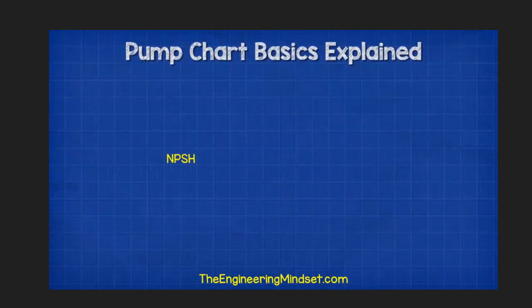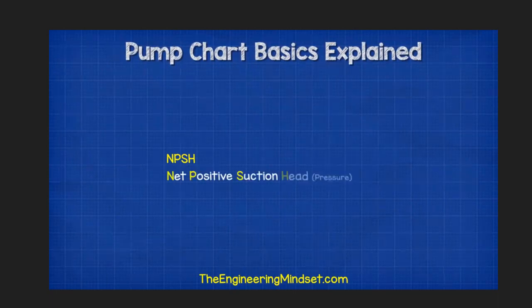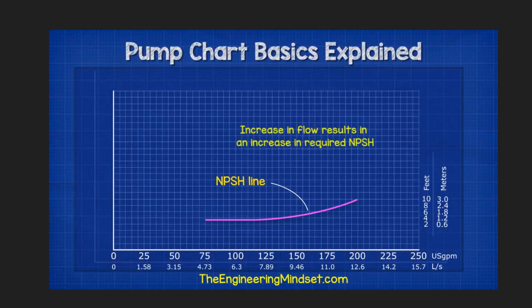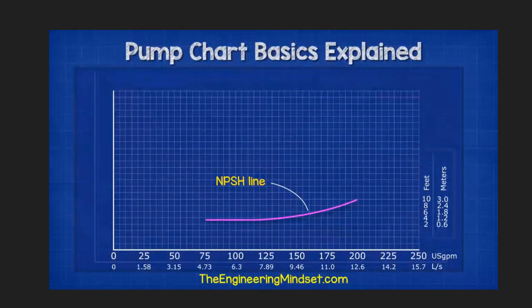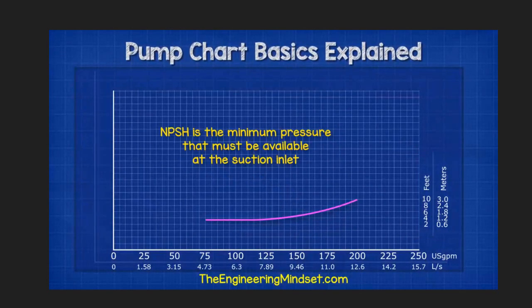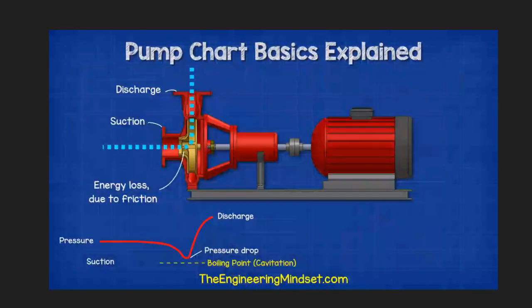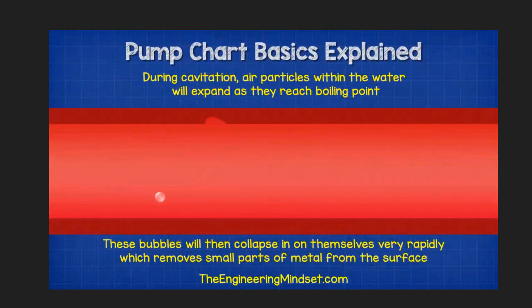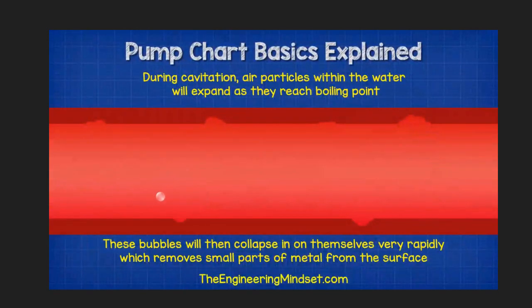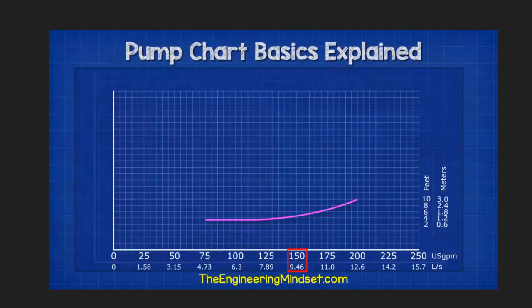NPSH is the required net positive suction head pressure. It usually has an upward curve, meaning as the pump flow rate increases, the NPSH value also increases. We measure this in meters or feet, sometimes kilopascals. The NPSH is the minimum pressure that must be available at the suction inlet of the pump to overcome entrance losses and avoid cavitation. Pump cavitation occurs where the pressure at the inlet reaches a low enough point that the water begins to boil, creating rapidly expanding and collapsing air bubbles which gradually destroy the surface of the pump and casing. For example, to move 150 gallons per minute we would require an NPSH value of around 4.9 feet.